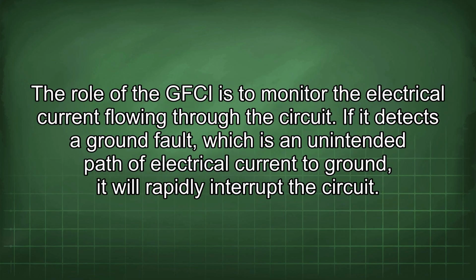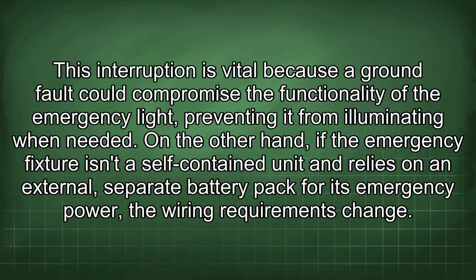The role of the GFCI is to monitor the electrical current flowing through the circuit. If it detects a ground fault, which is an unintended path of electrical current to ground, it will rapidly interrupt the circuit. This interruption is vital because a ground fault could compromise the functionality of the emergency light, preventing it from illuminating when needed.